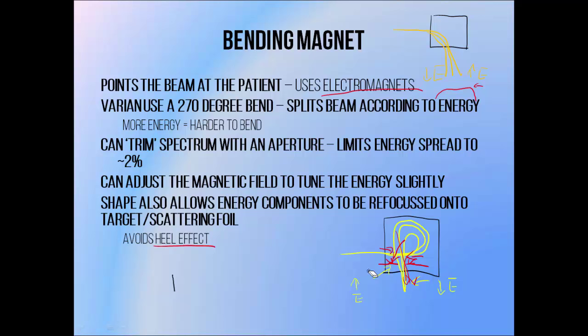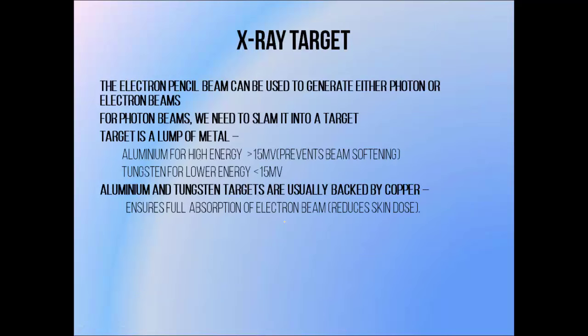Elekta linacs use a slightly different system known as a slalom design — a system of three different magnets that bends the beam in an S-shape. The electron beam that emerges from the bending magnet is quite thin, so we call it a pencil beam.